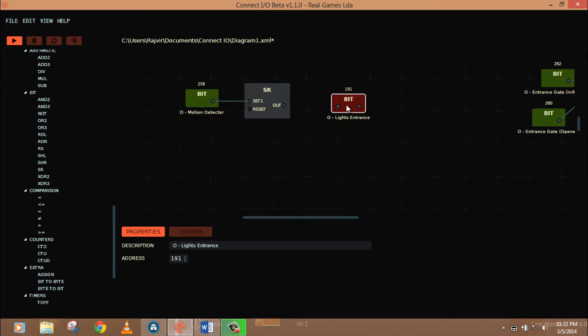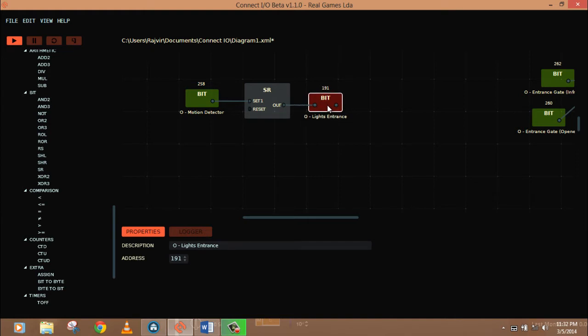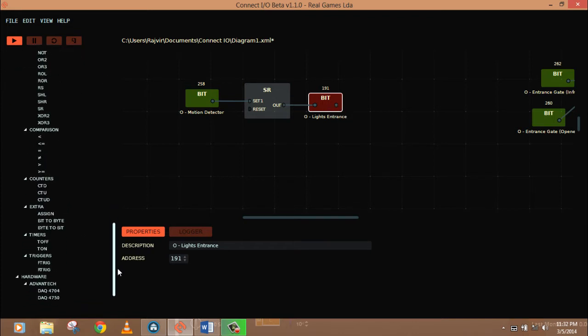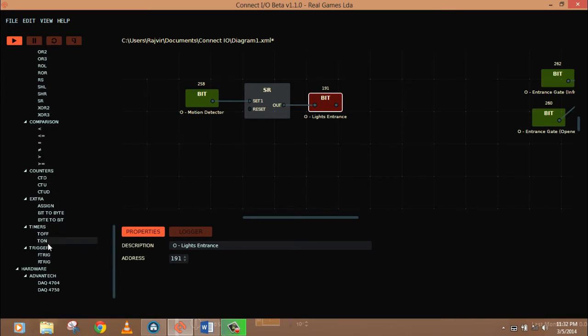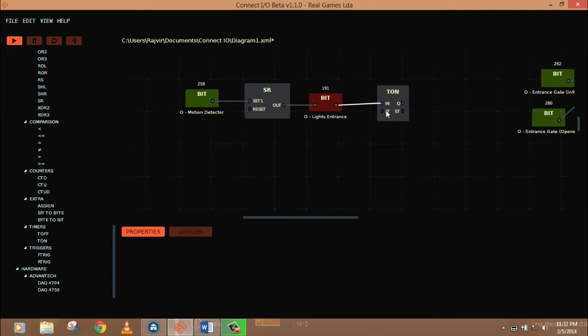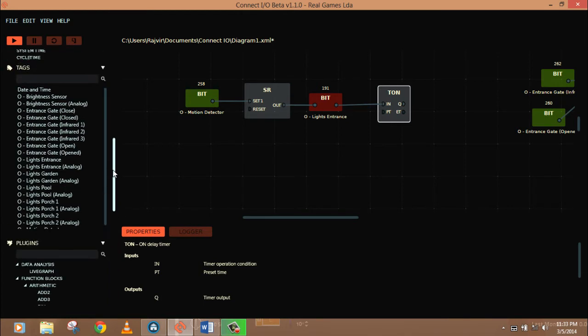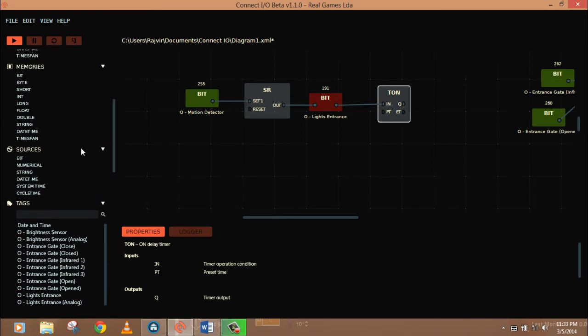Now we want a 10-second delay. Light should be on for 10 seconds, not five seconds. So what we're going to do is we're going to take a timer. From this bit, this bit is going to actuate a timer. You can find timers in this functional block over here: T-ON and T-OFF. Let's take T-ON. This is going to turn on the timer. Now PT is the process time, ET is your accumulator time. We have to give some time value to this timer that we can give using the source. You can go to numerical. This is a numerical value which you can connect to your timer.